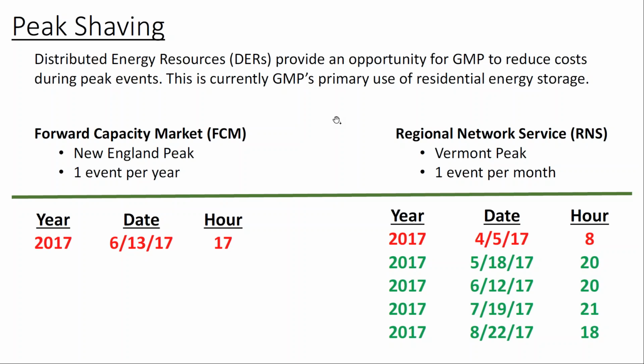And then our monthly peaks, you can see since we've got the batteries under our control 5 or 6 months ago at this point, we've been able to hit our peaks 4 out of the past 5 times, which is really great. One of the reasons for not being able to hit it in April is because in those shoulder months, there's very little load that fluctuates too much.